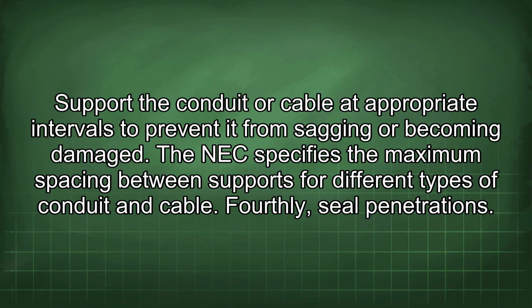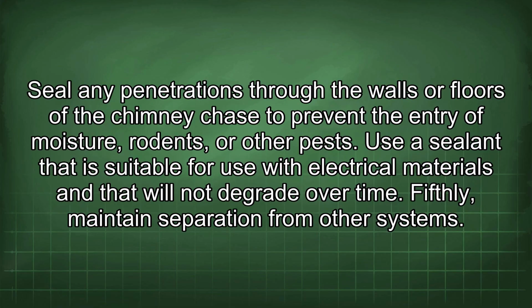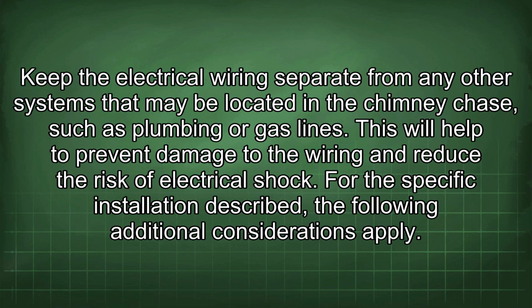Fourthly, seal penetrations. Seal any penetrations through the walls or floors of the chimney chase to prevent the entry of moisture, rodents, or other pests. Use a sealant that is suitable for use with electrical materials and that will not degrade over time. Fifthly, maintain separation from other systems. Keep the electrical wiring separate from any other systems that may be located in the chimney chase, such as plumbing or gas lines. This will help to prevent damage to the wiring and reduce the risk of electrical shock.